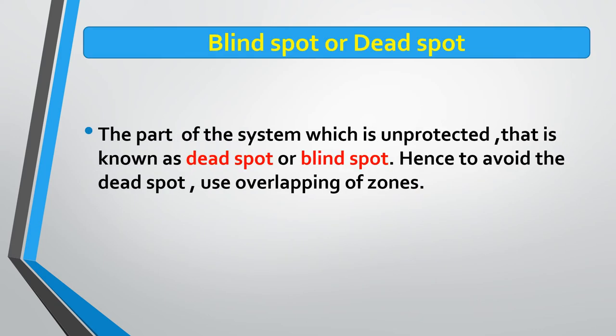One important term related to protection zones is the dead spot or blind spot. The part of the system which is unprotected is known as a dead spot or blind spot. To avoid dead spots, overlapping is used in protection zones — protection zones should be overlapped with each other to avoid dead spots or blind spots.